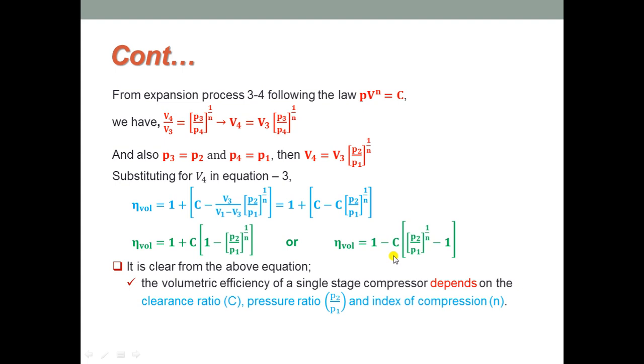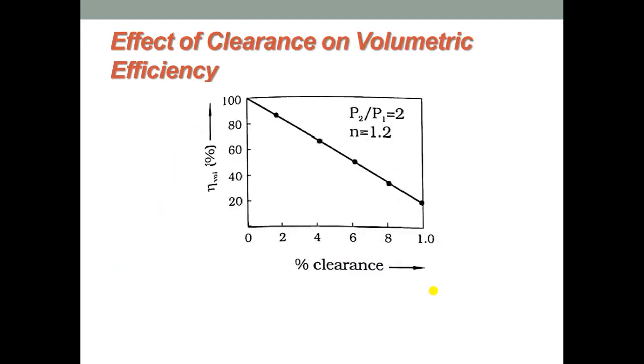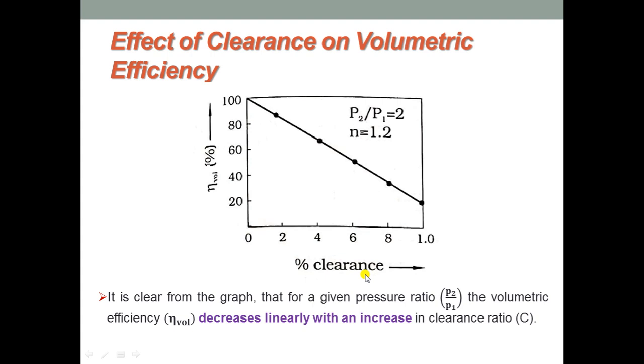It is clear from the above equation that the volumetric efficiency of a single-stage compressor depends on the clearance ratio C, the pressure ratio P2/P1, and the index of compression n. From the graph — where one axis shows percentage of volume and the other shows percentage of clearance — for a given pressure ratio, volumetric efficiency decreases linearly with an increase in clearance ratio.